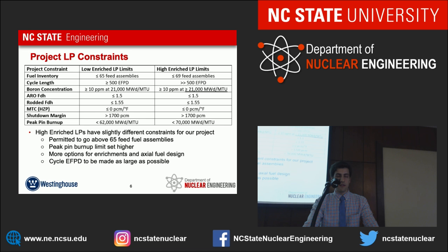For the cycle length, our target for EFPD, estimated full power days, is about 500 for the low enriched. For the high enriched, the interest is in seeing how far we can take the cycle using the high enriched fuel, and our limit is just above 500 estimated full power days. It wouldn't be effective for anything lower than that.